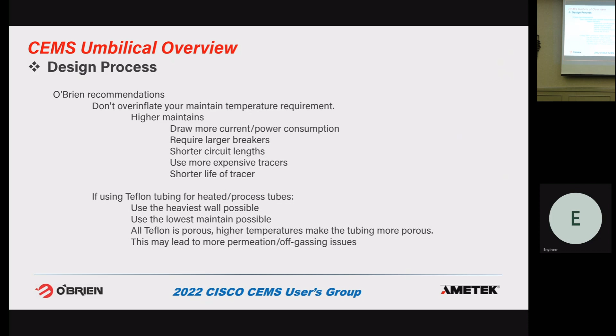So, tracer selection. We will select a tracer based on the maintain temperature, circuit lengths, voltage, all those things. And these are the four main styles of tracers we use: self-regulating, power limiting, constant power density, also called constant wattage or CPD, and series resistance. I'll go through each one of these and the pros and cons of each one. So self-reg, the pros are it can maintain up to 250F. There's actually a new tracer we can do up to 400F now.